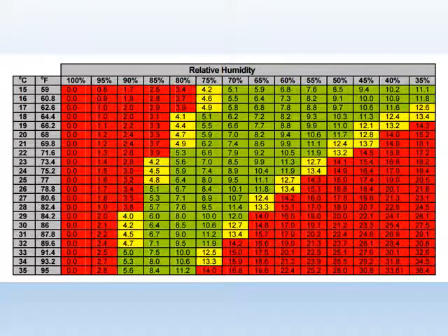from a plant's perspective. But it does not manage disease, because if you're only locking in your VPD, there are scenarios where you can have a perfectly acceptable VPD, but your humidity is at 90 to 85%. And you can also have a perfectly acceptable VPD, but your humidity is extremely dry. So in this case, you're sporulating, and in this place here you're growing powdery mildew. So even though you're locking in your VPD in these ranges, you're not managing disease.